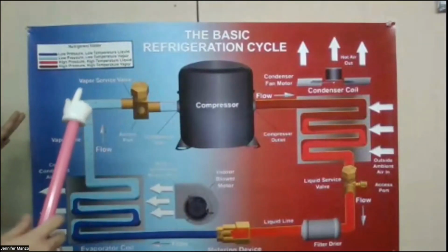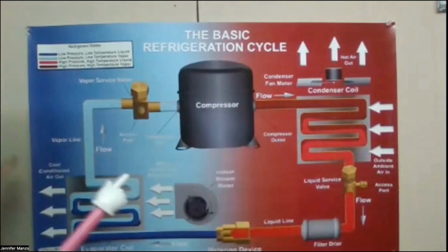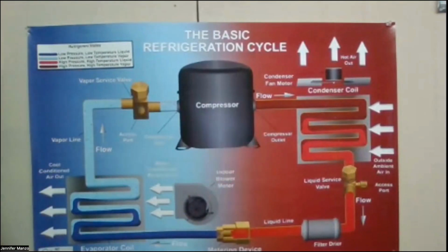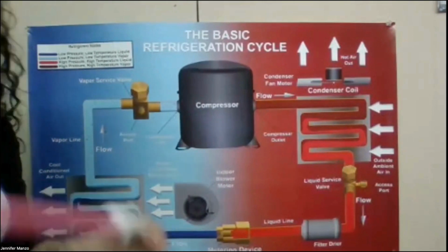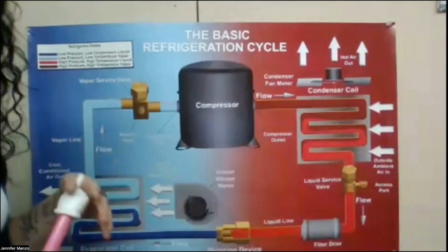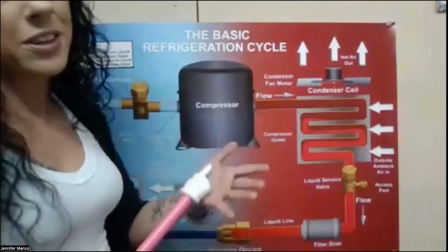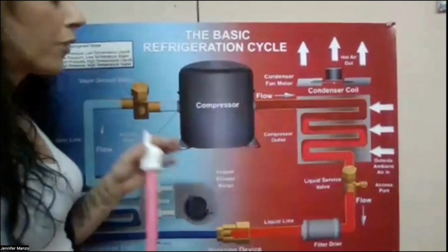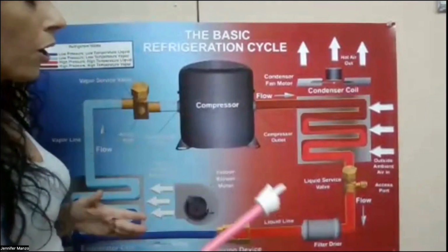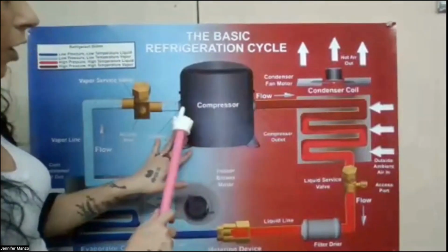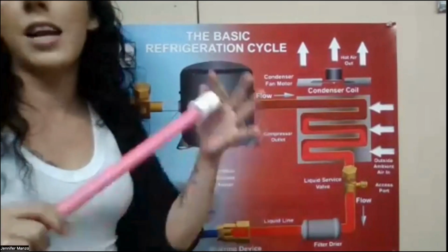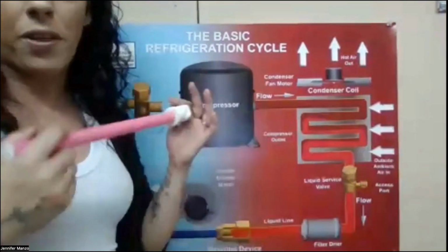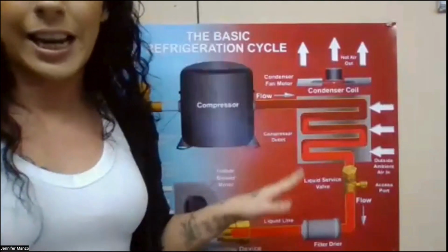So when we look at this, we see some different colorations, okay? And the reason for that is what you learned in the refrigeration theory course on SkillCat, phase change, right? We talk about water changing phase all the time. That's a huge part of our lives. Refrigerant also changes phase. So the compressor can only take what? Does anybody know what phase it should be in when it both enters and leaves the compressor? Temperature aside, should it be a vapor or a liquid? Low pressure vapor to high pressure vapor. Right. Either way, vapor, right? It cannot take liquid.